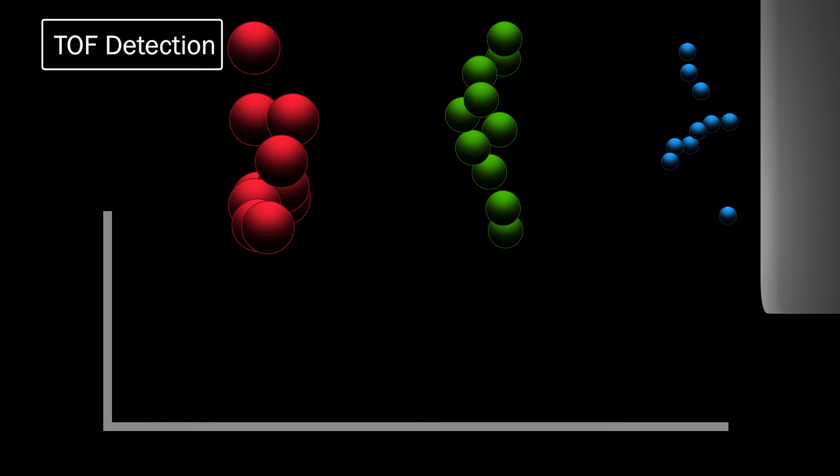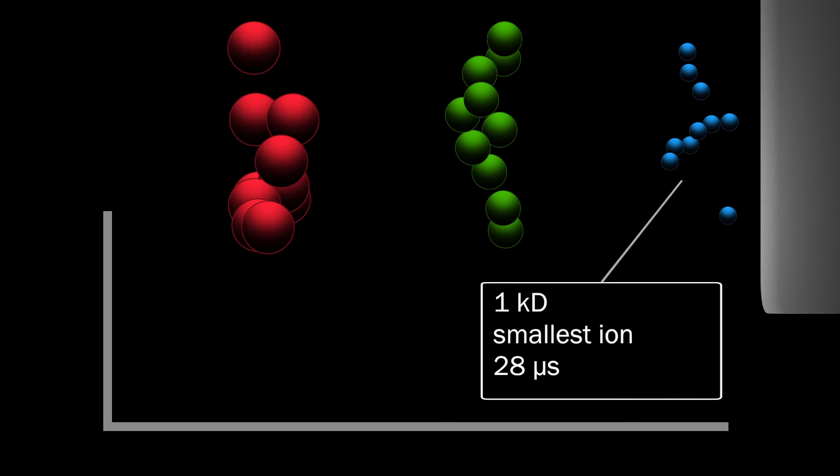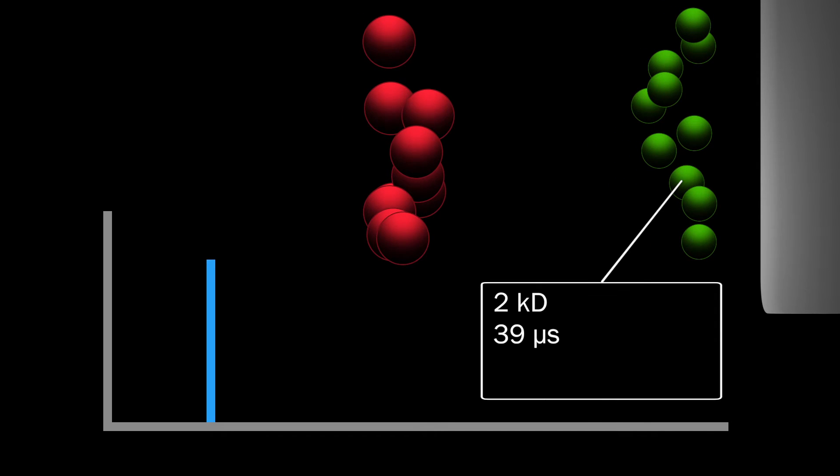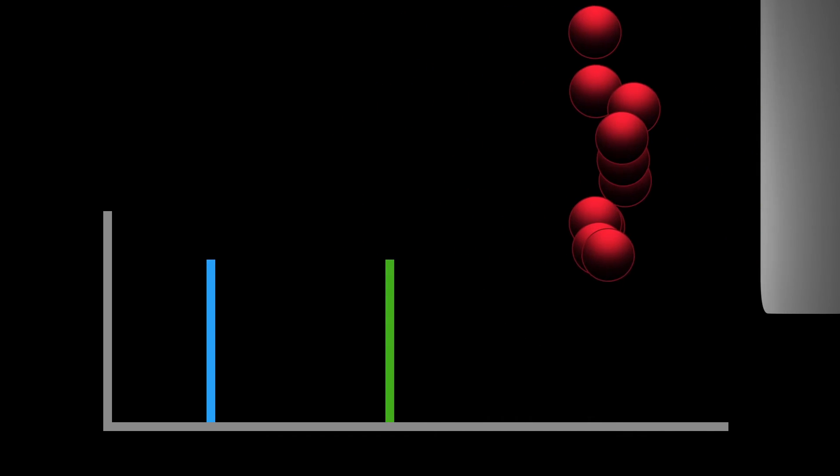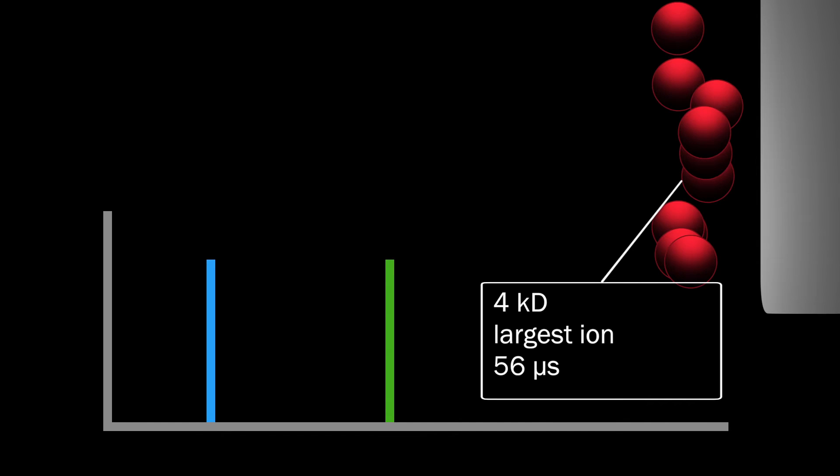The TOF detector then records the time it takes for the groups of ions to travel a certain distance. From our previous examples, for a standard 1.5-meter flight, the smallest ion would reach the detector in around 28 microseconds, the next at around 39 microseconds, and the largest ion in around 56 microseconds.